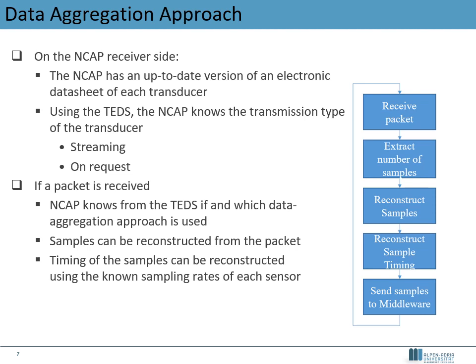Then, using the received frame number and comparing it with the last received frame number stored locally on the NCAP, the timeline of the received packet can be verified. Additionally, using the information about the measurement rates of each sensor extracted from the electronic datasheet together with the frame number, the timestamp of each sample of each sensor can be reconstructed. If a middleware is defined, the reconstructed samples are sent to the middleware.